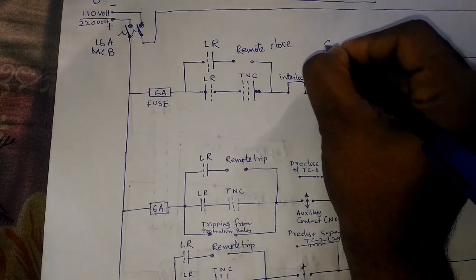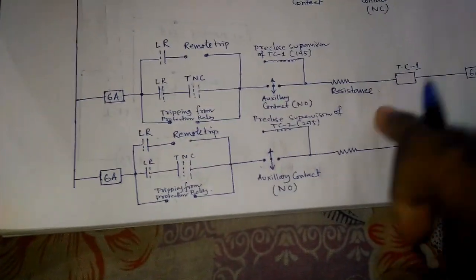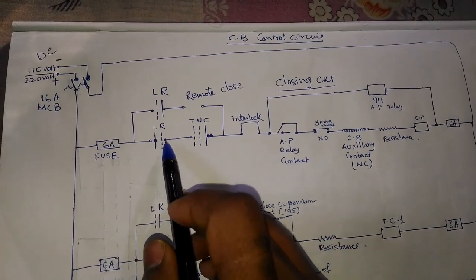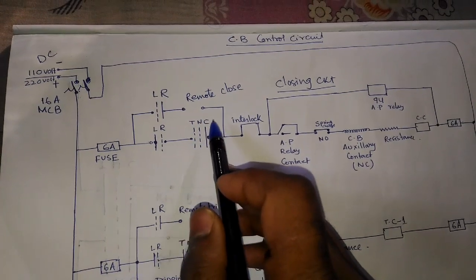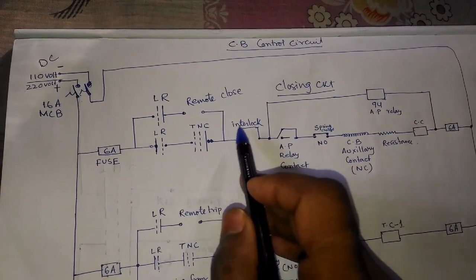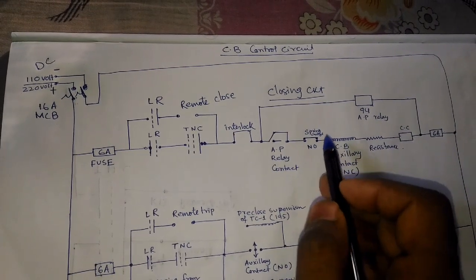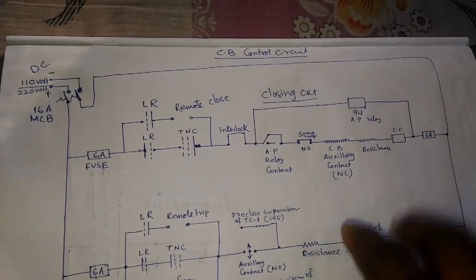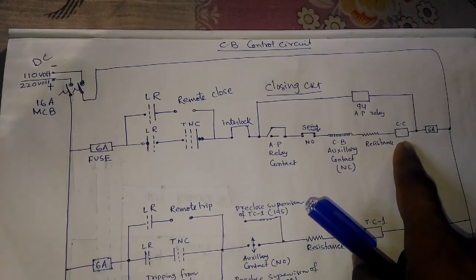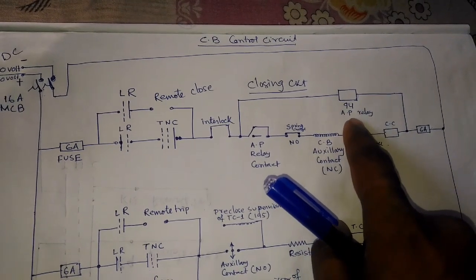We are now discussing the closing circuit. This includes the closing circuit and two tripping circuits. First, there is the local-remote selector switch, then the TNC (Trip-Neutral-Close) switch, followed by the pistol grip spring mechanism. This is the interlock, this is the anti-pumping relay contact, the spring charge normally open contact, and after spring charge it is an NC contact. This is the circuit breaker auxiliary contact — it is NC — followed by a resistance before the closing coil, a 6-ampere fuse, and the anti-pumping relay 94.